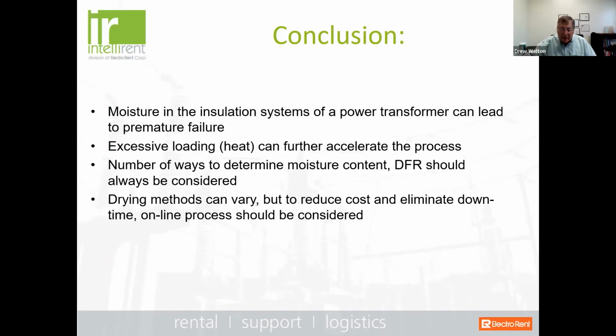And this was a problem that a utility had a number of years ago. They had free breathing conservators on a lot of old transformers, and the desiccants weren't well maintained, and they had a huge moisture issue. In fact, they had a moisture issue in one particular transformer. I can remember seeing this at a TechCon conference. It was so bad that the actual transformer blew up, in the seam that blew apart in the tank, some guy was actually standing in. Luckily, it didn't catch fire, but it was a catastrophic situation.